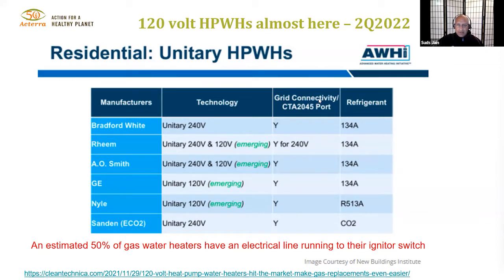There's also a new standard called grid connectivity, CTA 2045. That allows the power company, if you let them, to basically manage your heat pump water heater, turning it on and off based on when the grid is running low on electricity or when energy prices are really low. It turns out about 50% of existing gas water heaters already have an electric line running to their igniter switch, so running one of these 120 volt heat pump water heaters won't require a lot of electrical work since you already have that line running there.